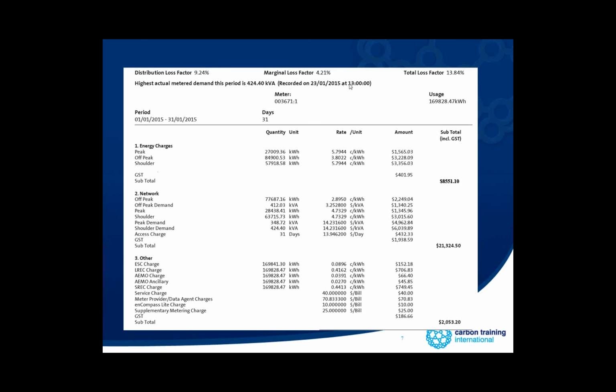You can see here a little bit of extra information on the demand. 424.4 was the peak recorded for that actual month, and it tells you the date and the actual time. So if you go back through your last 12 months of bills, and it always happens to be on a Tuesday at 1 o'clock, you can go and ask, well, what happens on a Tuesday at 1 o'clock, or what happens every day at 1 o'clock that's causing this consistency? And you'd be surprised in most businesses how consistent that is.